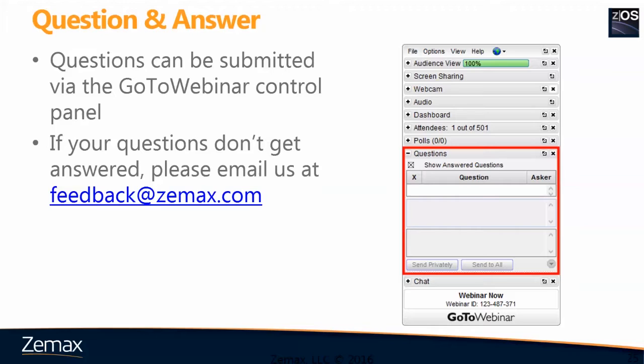Here's a follow-up on the lens reflection question — would two reflections be acceptable? It depends on the percentage. If you have one reflection but it is very strong relative to the image, it will destroy your image and the objective is useless. On the other hand, if you have 10 very tiny reflections where the percentage of light relative to the image is very small, even 10 or more is not an issue. It all depends on the relative strength — how many percent of the light is relative to your image.